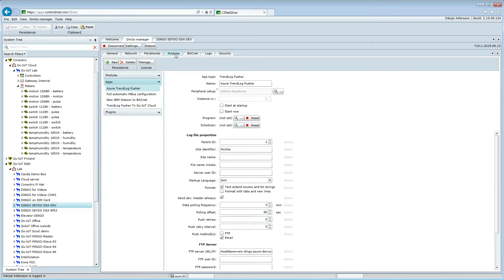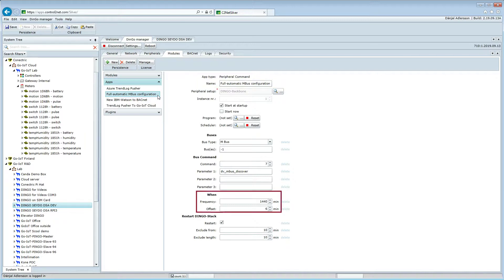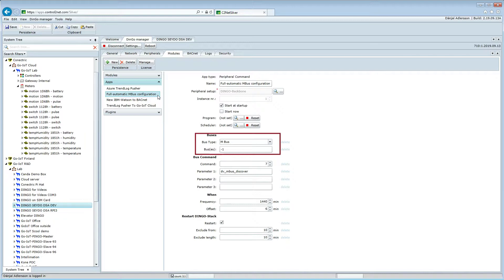I have named this instance Full Automatic mBus Configuration. This application is configured to run every 24 hours, with an offset of 6 minutes. The application is configured to use the mBus, and the negative 1 integer means we are using all buses.